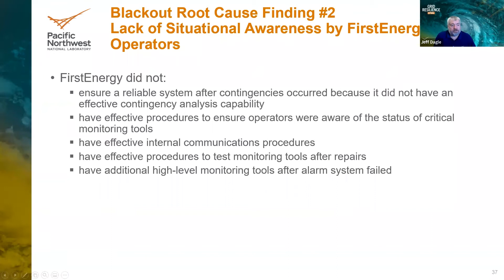We did, on the Blackout investigation team, we did have a question about whether or not the wind speed might have had an issue because it was not windy at all that day. Akron Airport, near the epicenter of all this, reported 0 knots wind speed at the airport at 3 o'clock in the afternoon and at 4 o'clock in the afternoon. And the industry standard for rating overhead transmission lines is you assume a little gentle breeze to help cool the conductors. And so that was a concern. Did we make a mistake in terms of rating those conductors by not assuming the possibility of 0 wind?